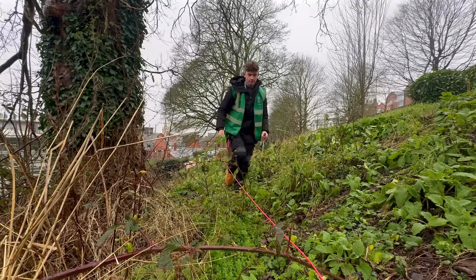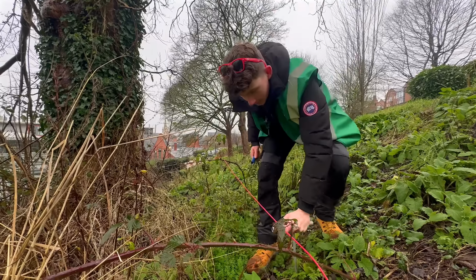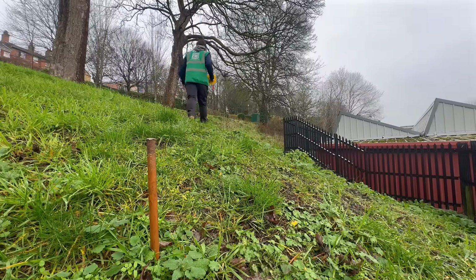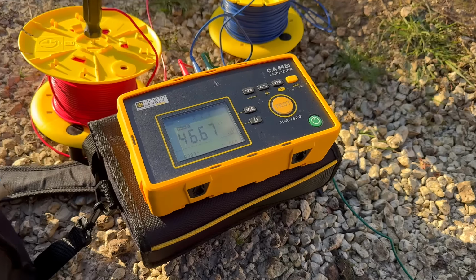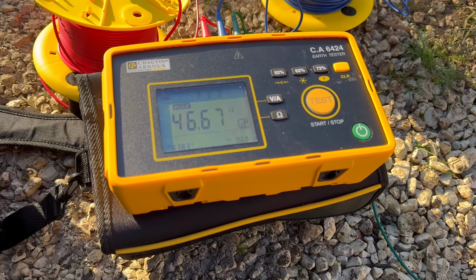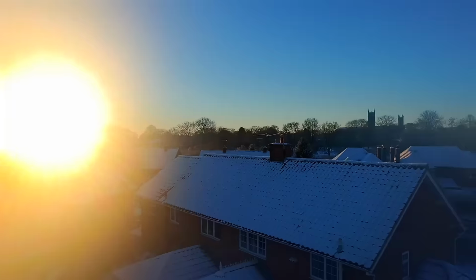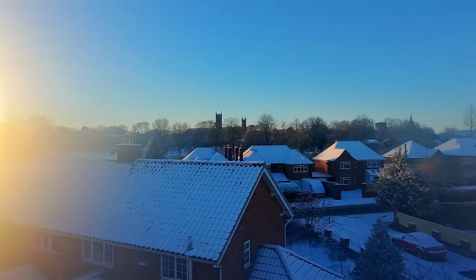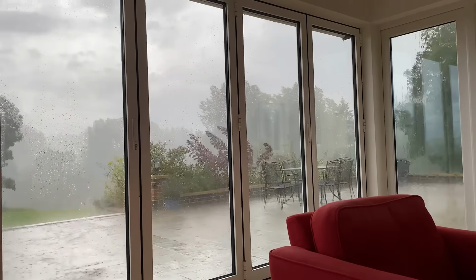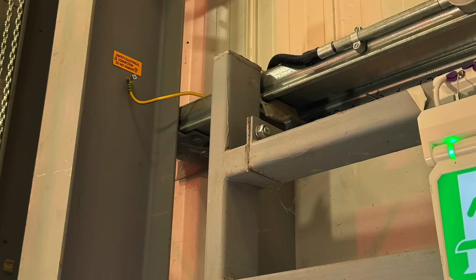But what about the maximum permitted value allowed for earth electrode resistance testing? Again, a number you may have heard of is 200 ohms. And that is right, because anything above 200 ohms is considered unstable. What we're after is a low stable reading, and soil conditions can affect those readings dramatically. Frost, snow, wet weather, all of these will impact the resistance of an earth electrode in the soil. And we are going to be finding out how these conditions affect earth electrode resistance test readings in the next video. But there is one more thing you need to be careful of when you're doing earth electrode resistance testing, and that is parallel paths.